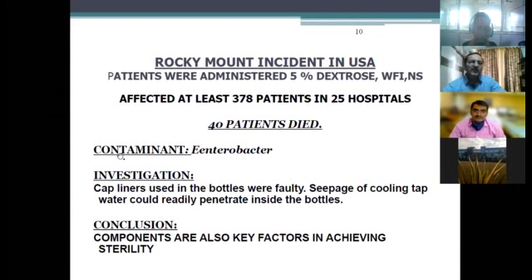Another thing is patients were administered again here 5% dextrose water for injection, normal saline. It affected at least 378 patients in 25 hospitals across US. 40 patients also died. Again, contamination was enterobacter. Investigation was done. The cap liners which were used in the bottles were faulty. So seepage of cooling tap water could readily permeate inside the bottle. So when the cycle was over, they used to spray tap water inside the autoclave for cooling the bottle so that they can be taken out fast and they can be taken for packing.